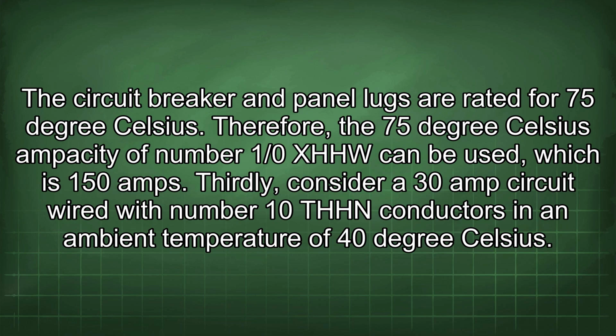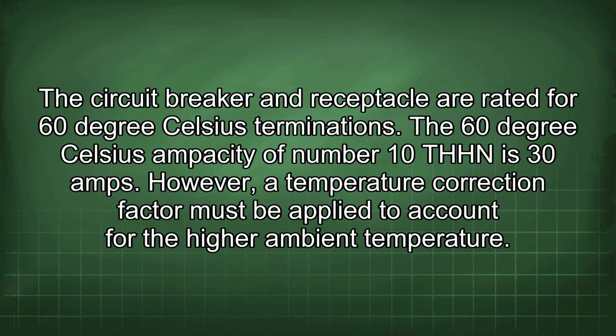Thirdly, consider a 30 amp circuit wired with number 10 THHN conductors in an ambient temperature of 40 degrees Celsius. The circuit breaker and receptacle are rated for 60 degrees Celsius terminations. The 60 degrees Celsius ampacity of number 10 THHN is 30 amps. However, a temperature correction factor must be applied to account for the higher ambient temperature.